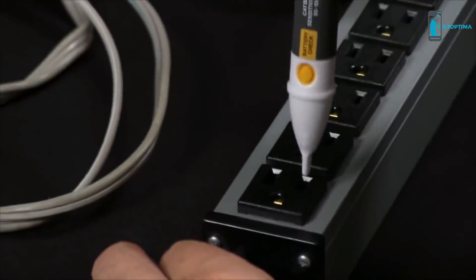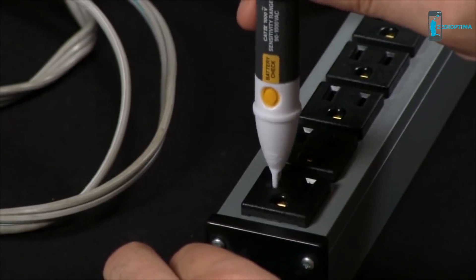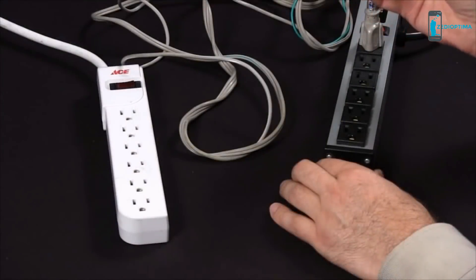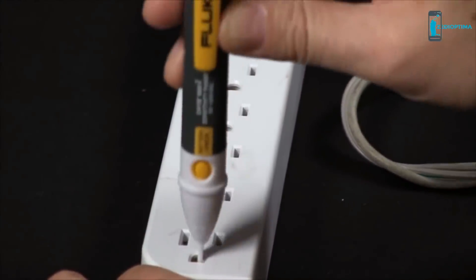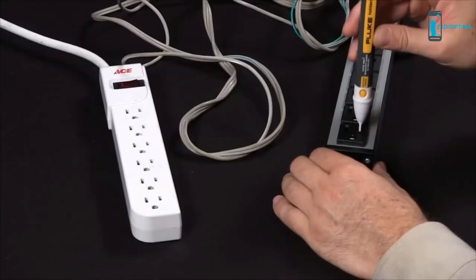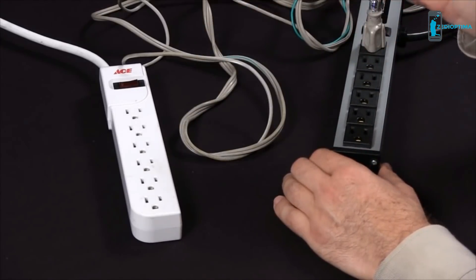Place the 2AC into the hot side and then place it into the neutral. Another method you can employ is a three-point test. Check the additional power strip and see there is no power anywhere in the hot, neutral, or ground. Go back and check it against a known good circuit — see that you do have power — and you can make the determination that you have lost power in the subsequent power strip.